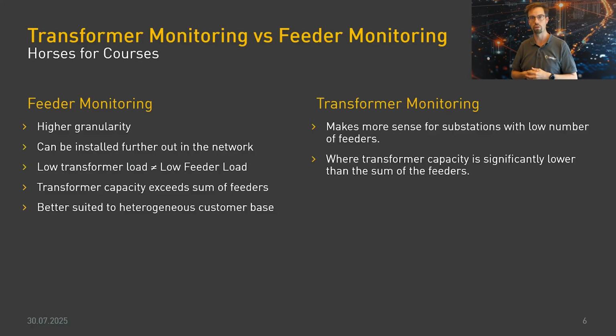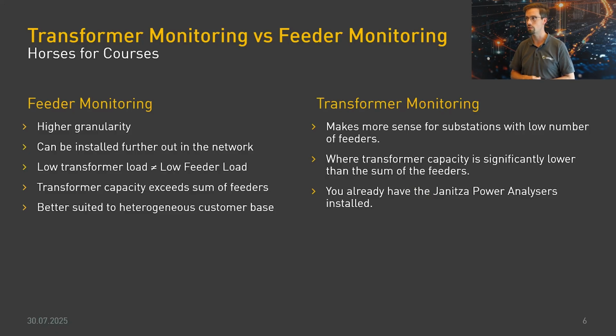So look at the smaller transformers with low numbers of feeders, and situations where transformer capacity is significantly lower than the feeders. Over time the number of feeders may have grown, and each feeder may have the right capacity, but that growth has put the transformer out of balance relative to the feeders. In that case it makes more sense to monitor the transformer, since that's probably your weakest link in the chain. Even though you have many feeders and it may be interesting to see what's happening on them, the transformer is the critical part you need to monitor.